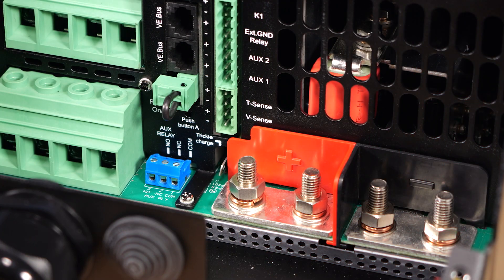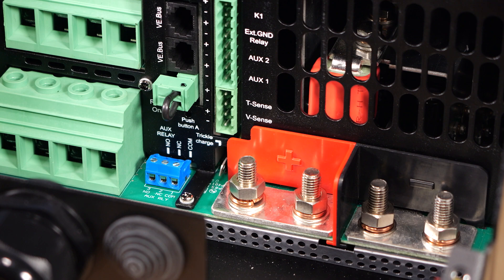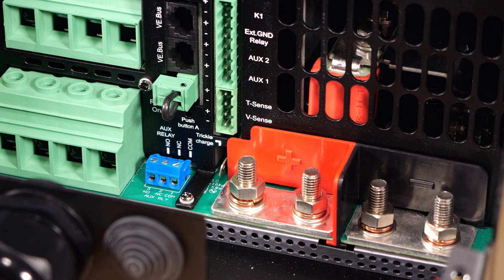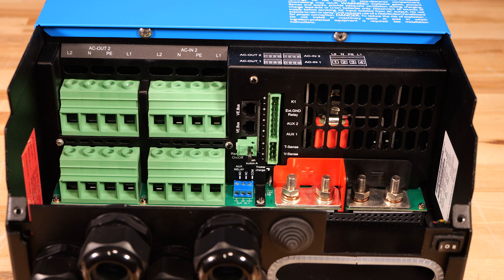Last but not least, we have the optional remote voltage sensing input so that we can measure the voltage at the batteries and zero out any voltage drop on the DC power cables feeding the inverter. It's worth noting that this inverter doesn't have an input for the external current sensor like some of the multi-plus series that gets used on residential ESS systems.